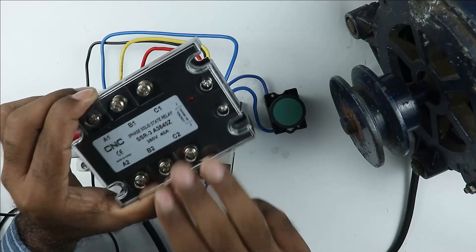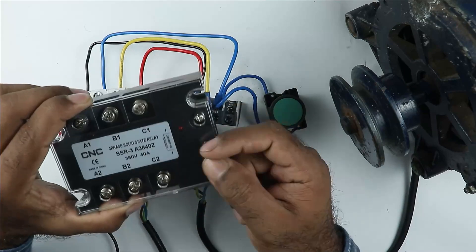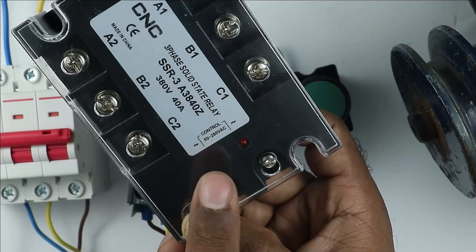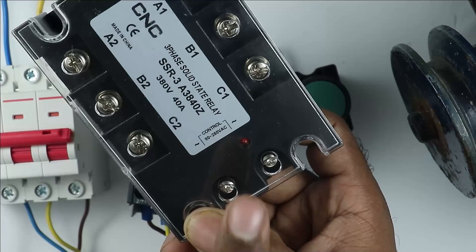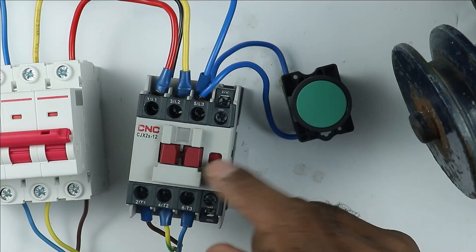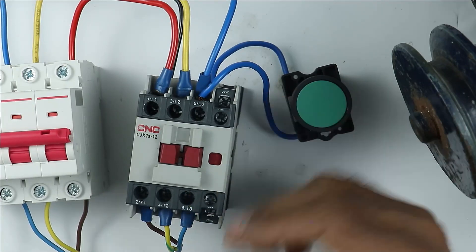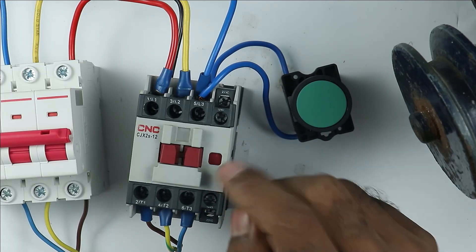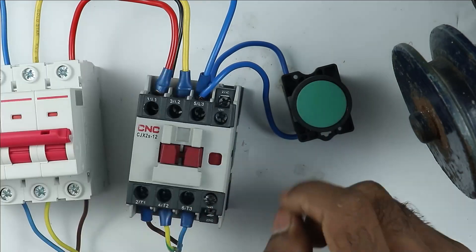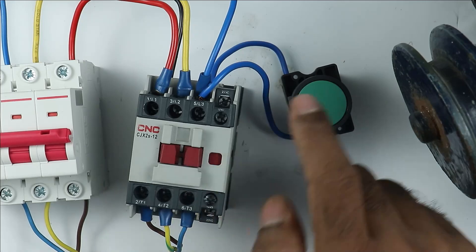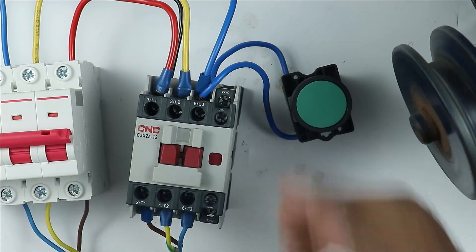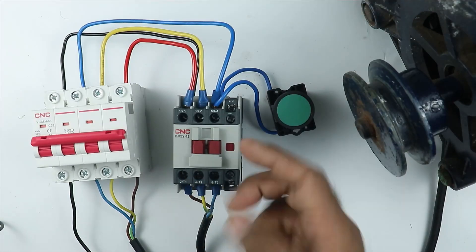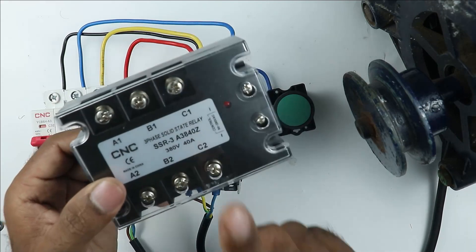Apart from this in the solid state relay the voltage to control this is much more. You can see on this relay here 90 to 280 volt AC is written. It means by providing 90 to 280 volt we can operate this relay. But in our contactor it is written 230 volt. Only 10% of 230 volt can be more or less as adjusted by the contactor. If you provide 90 volt power supply to contactor then it won't turn on. So the limitations I told you about contactor can be overcome by using this type of solid state relay.